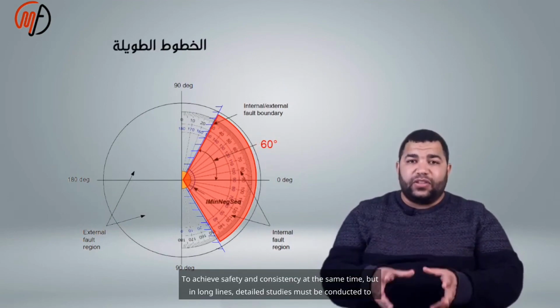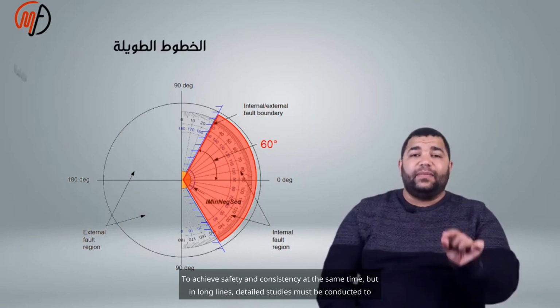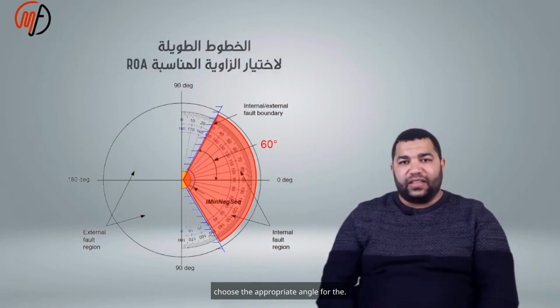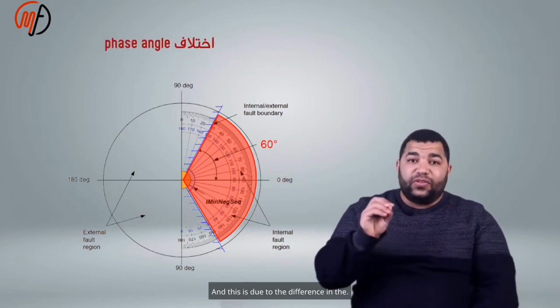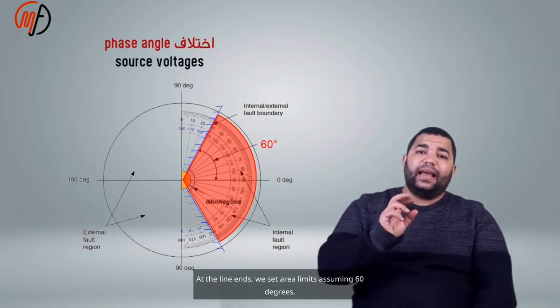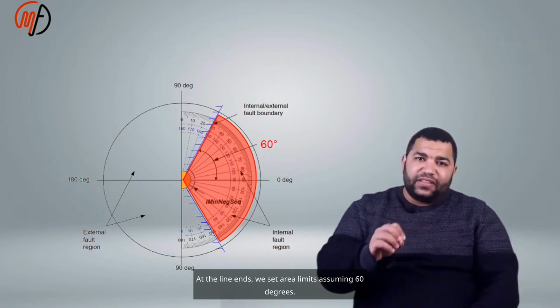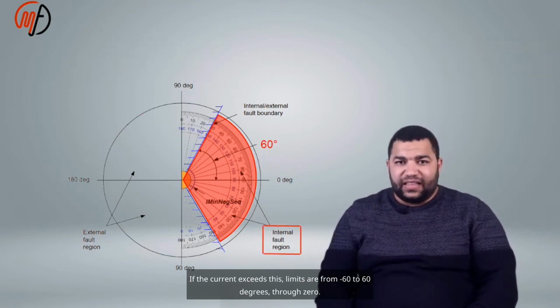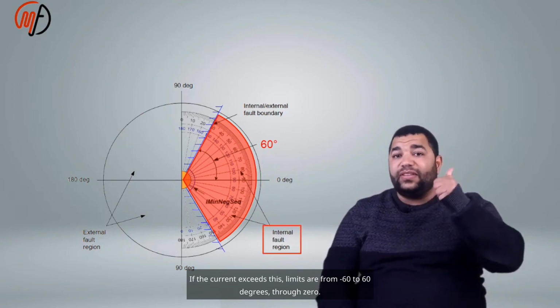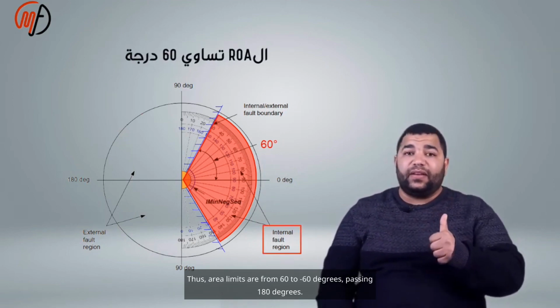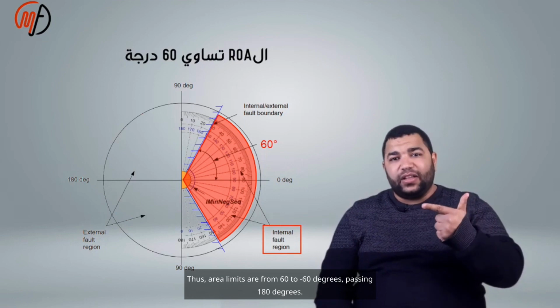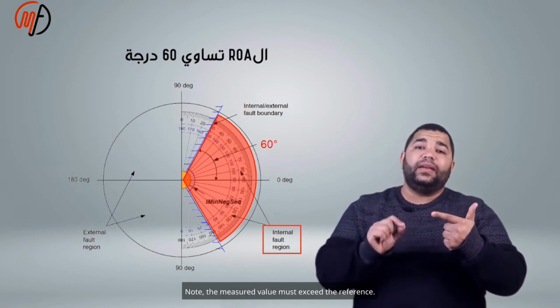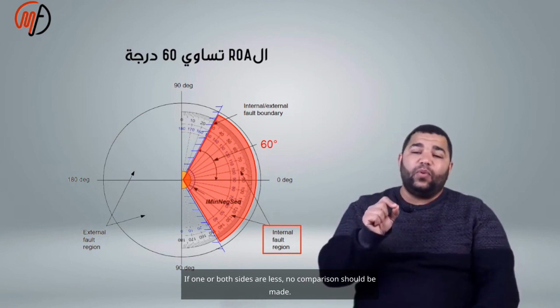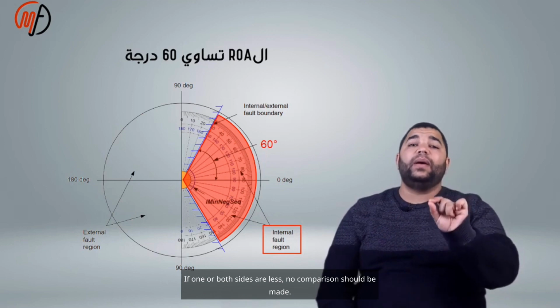But in long lines, detailed studies must be conducted to choose the appropriate angle, and this is due to the difference in current at the line ends. We set area limits assuming 60 degrees. If the current exceeds this, limits are from minus 60 to 60 degrees through 0. Thus, the restraint area limits are from 60 to minus 60 degrees, passing through 180 degrees. Note, the measured value must exceed the reference. If one or both sides are less, no comparison should be made.